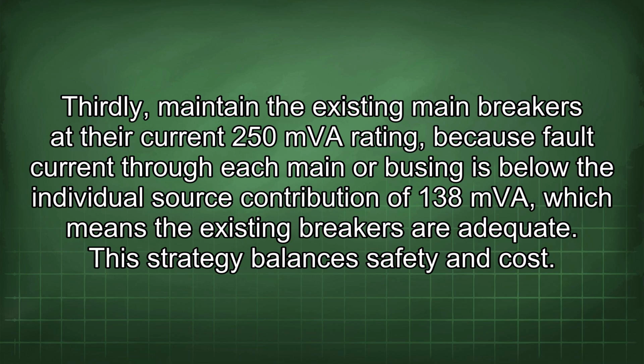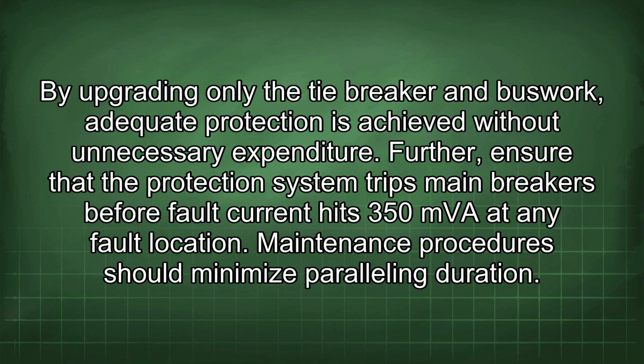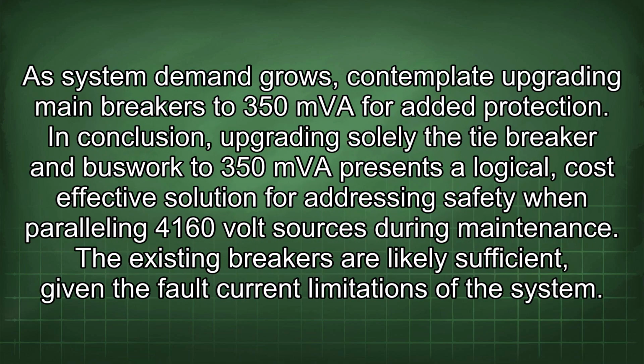This strategy balances safety and cost. By upgrading only the tie breaker and buswork, adequate protection is achieved without unnecessary expenditure. Further, ensure that the protection system trips main breakers before fault current hits 350 MVA at any fault location. Maintenance procedures should minimize paralleling duration. As system demand grows, contemplate upgrading main breakers to 350 MVA for added protection.